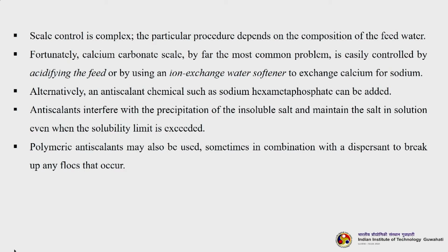Alternatively, an anti-scalant chemical such as sodium hexametaphosphate can be added. This will help in reducing the scale formation. It binds to the scale forming compounds, and those can be removed from the feed water. Anti-scalants interfere with the precipitation of the insoluble salt and maintain the salt in solution even when the solubility limit is exceeded. Polymeric antiscalants are also available nowadays, sometimes in combination with a dispersant to break up any floc that occurs in the feed water.